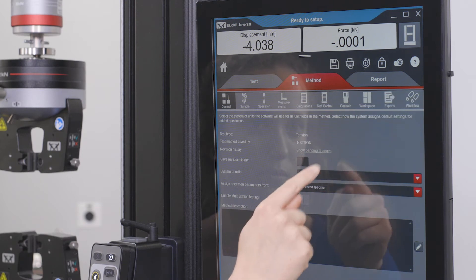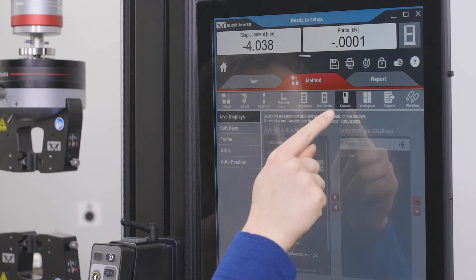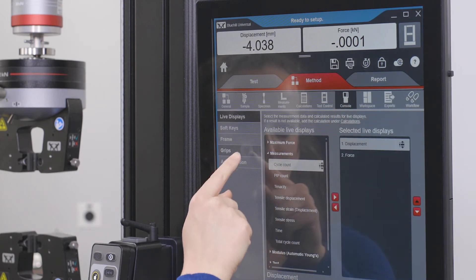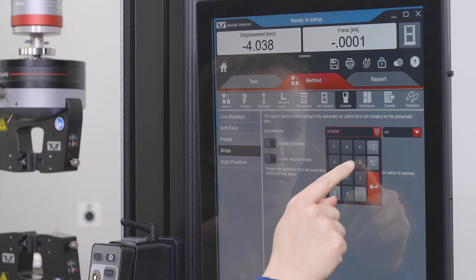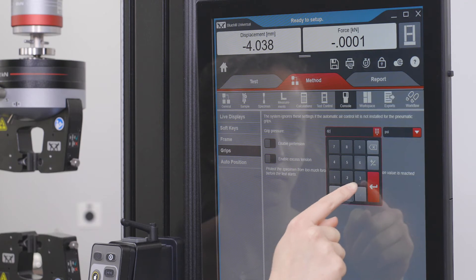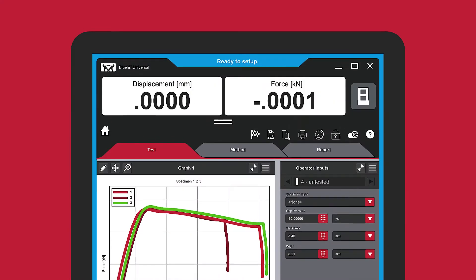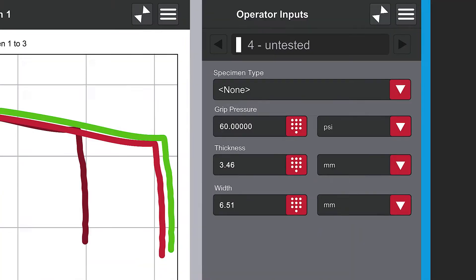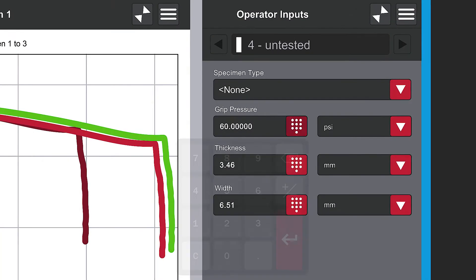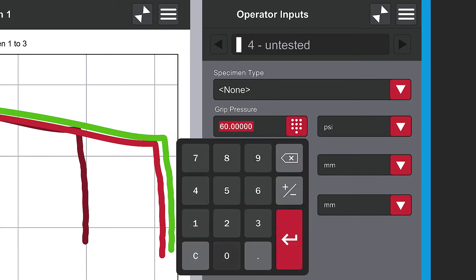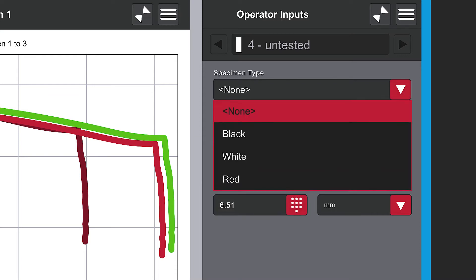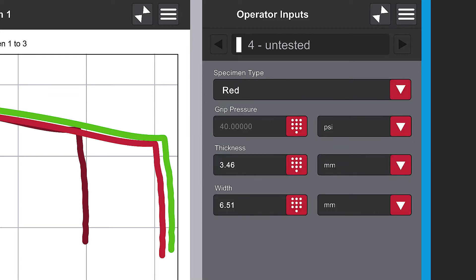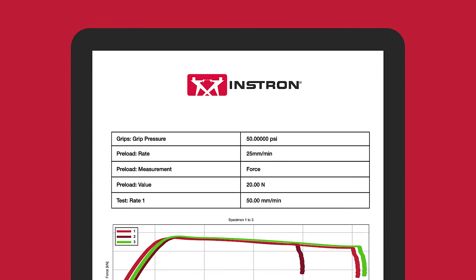The grip pressure is defined inside the test method, which dramatically improves workflow efficiency for users. Grip pressure can be set as an operator input or linked to a choice input, such as specimen type. This also allows for grip pressure to be displayed in the test results.